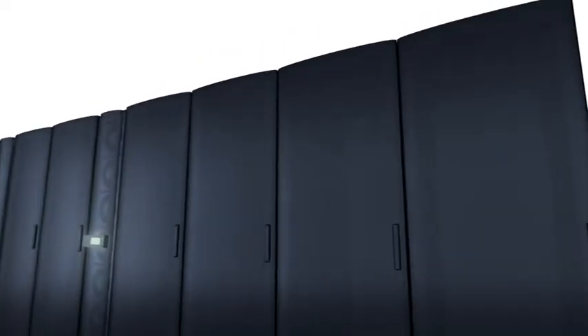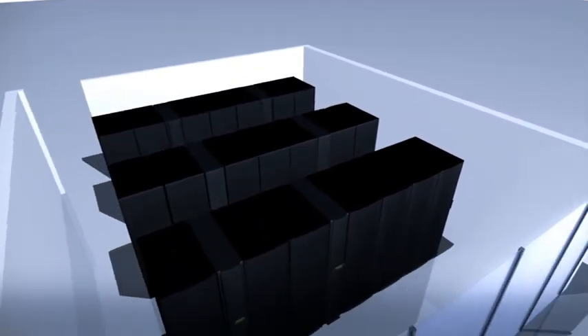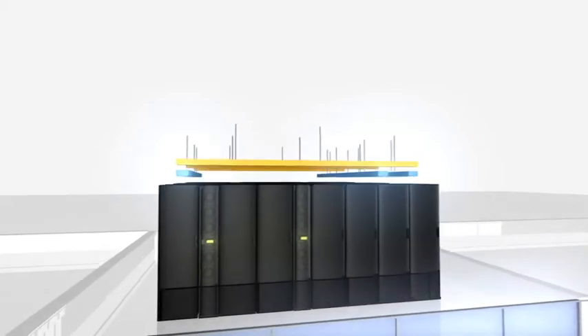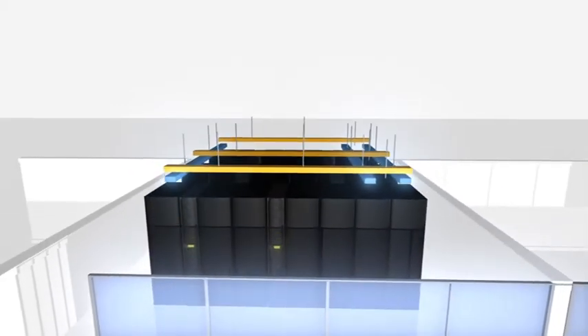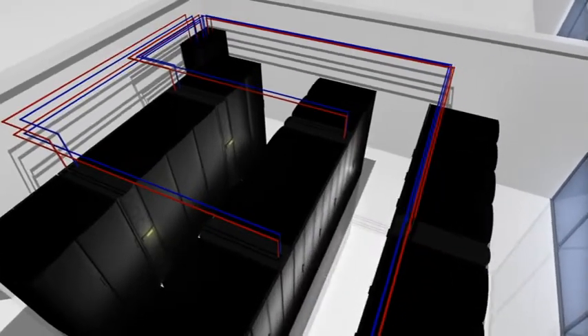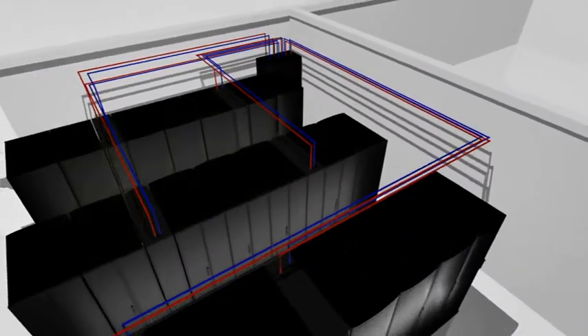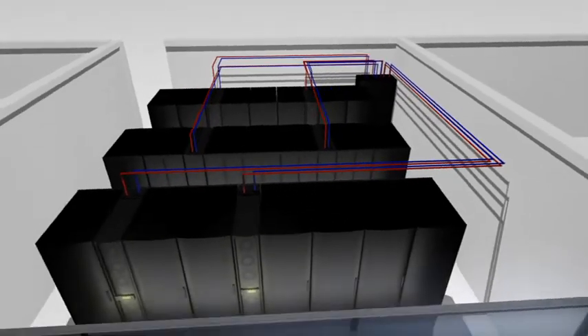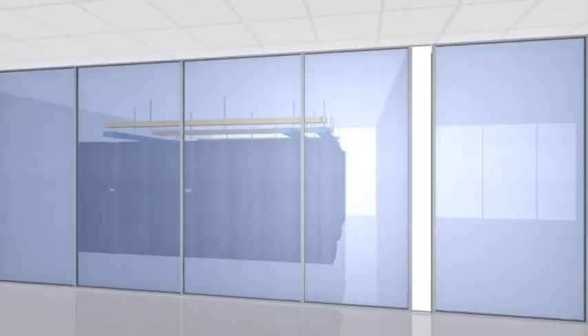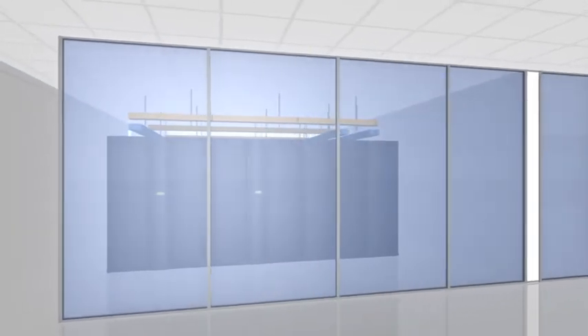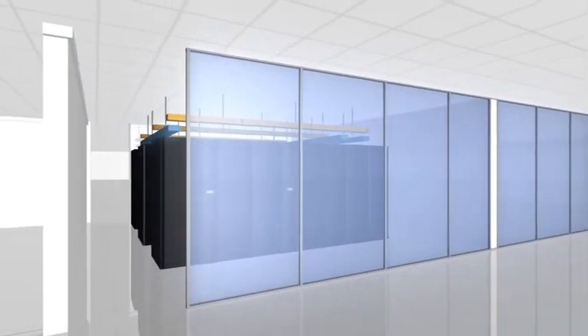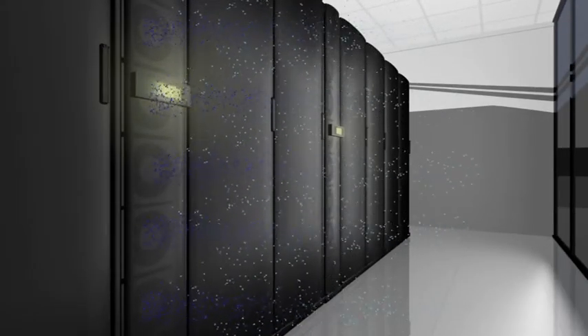The second part of the installation, Phase 2, included the installation of the power protection system, UPS, the installation of the power distribution to the IT racks, and the installation of the high-precision cooling system and infrastructure management applications. The data centre layout is organised in 3 rows in a hot and cold aisle arrangement. The in-row or in-line cooling units are high-precision systems designed to deliver up to 30 kilowatts of cooling capacity per unit, depending on the environment.